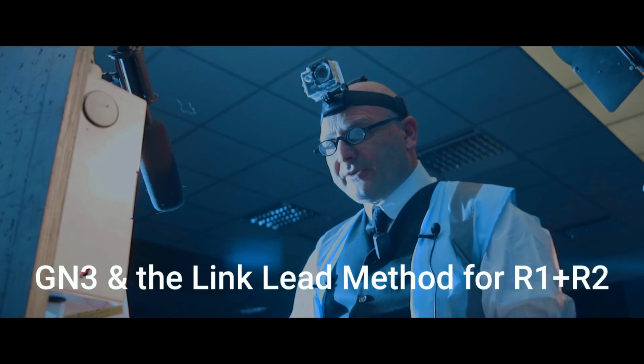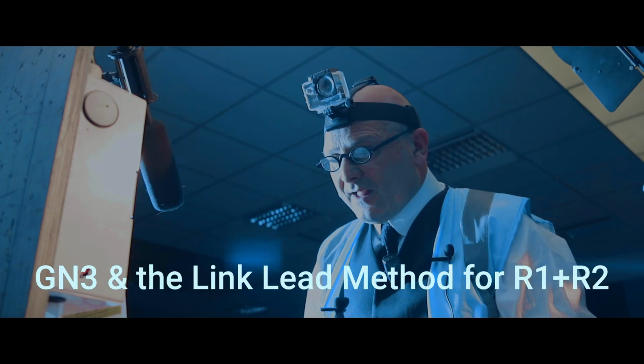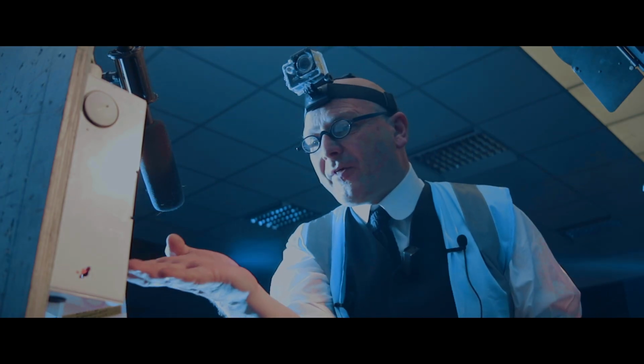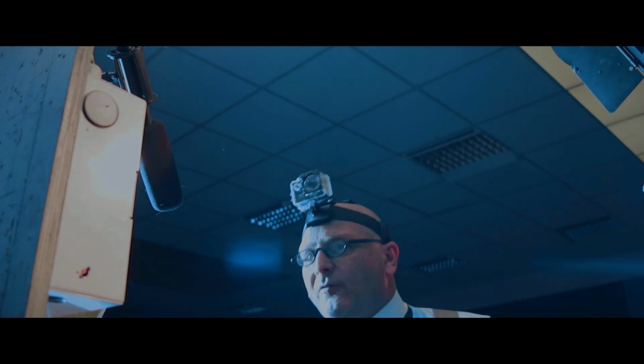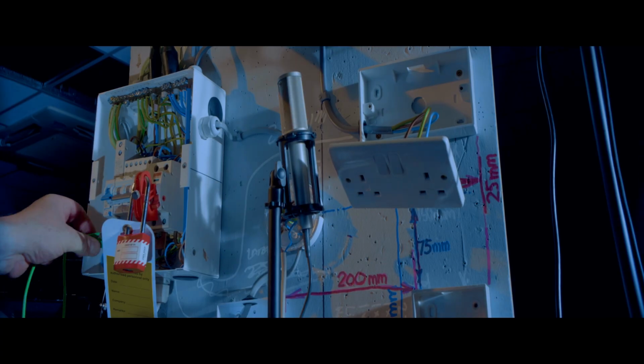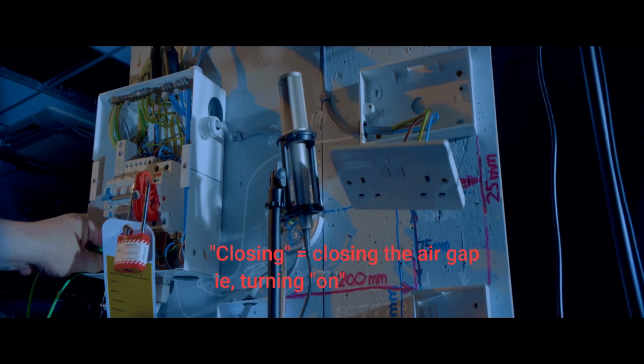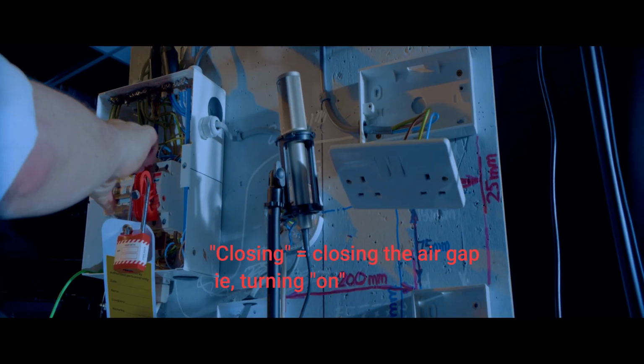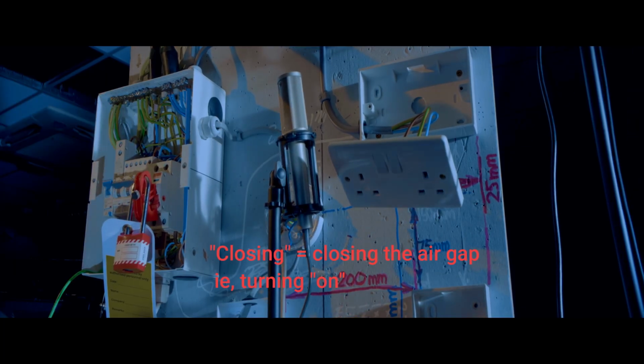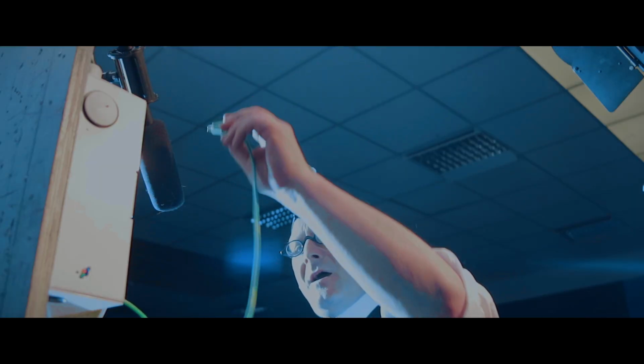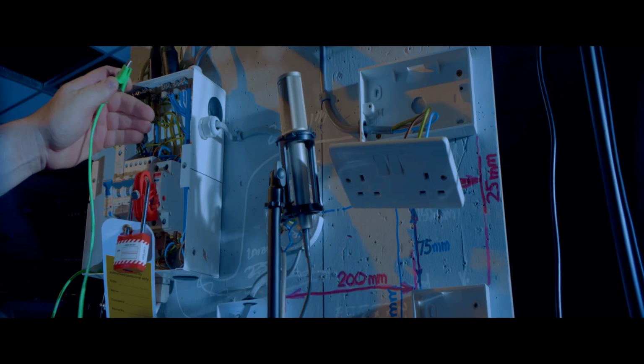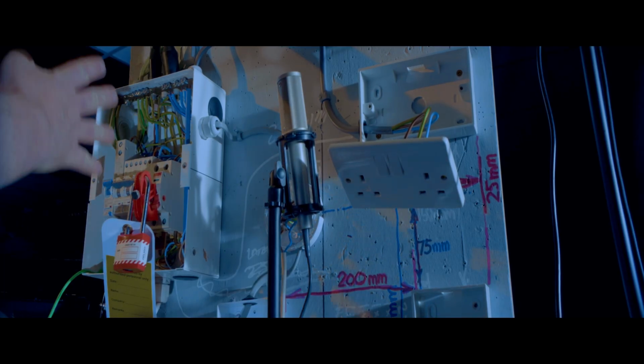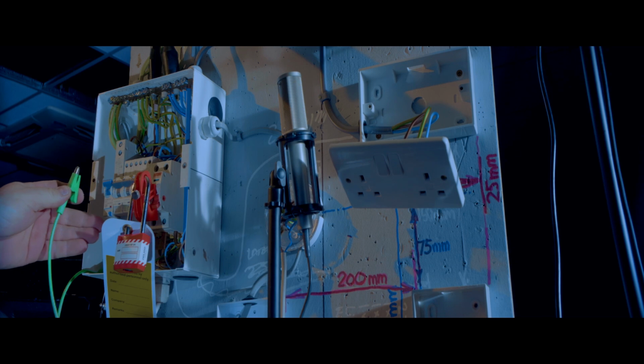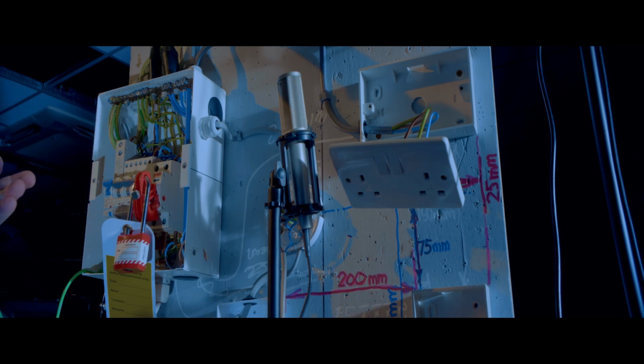Page 43 of Guidance Note 3 tells me that I can show the bus bar to the origin of all the circuits by closing all the overcurrent protective devices, not the main switch obviously. So the bus bar now has continuity with all those brown leads.